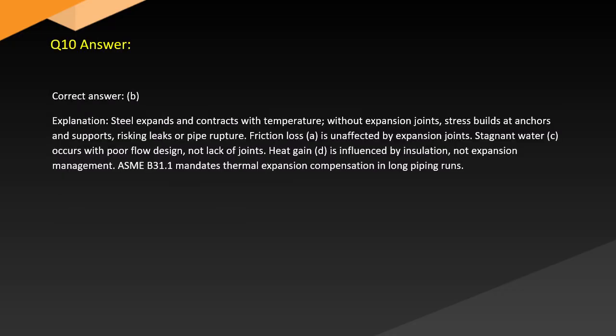Answer. Correct answer. B. Explanation. Steel expands and contracts with temperature. Without expansion joints, stress builds at anchors and supports, risking leaks or pipe rupture. Friction loss, A, is unaffected by expansion joints. Stagnant water, C, occurs with poor flow design, not lack of joints. Heat gain, D, is influenced by insulation, not expansion management. ASME B31.1 mandates thermal expansion compensation in long piping runs.